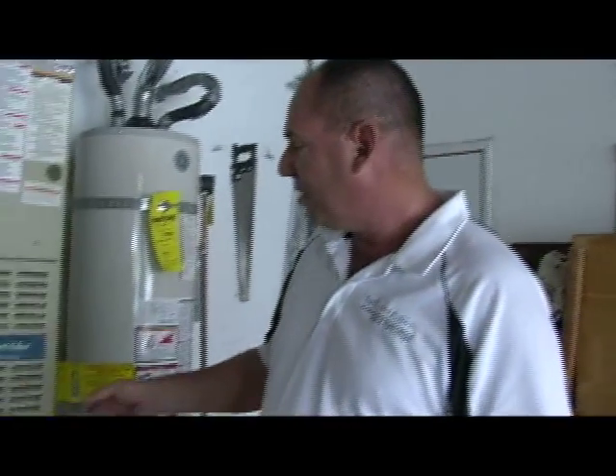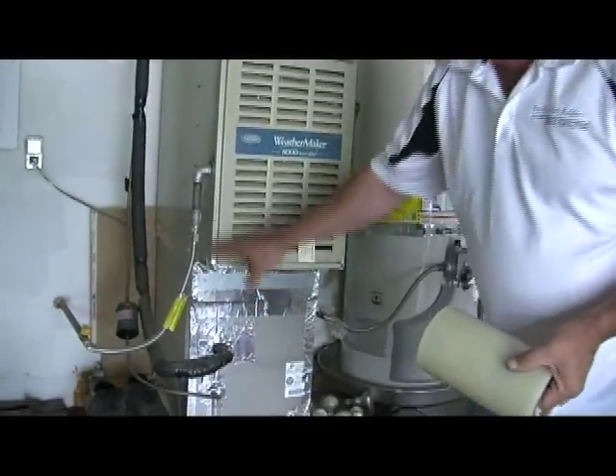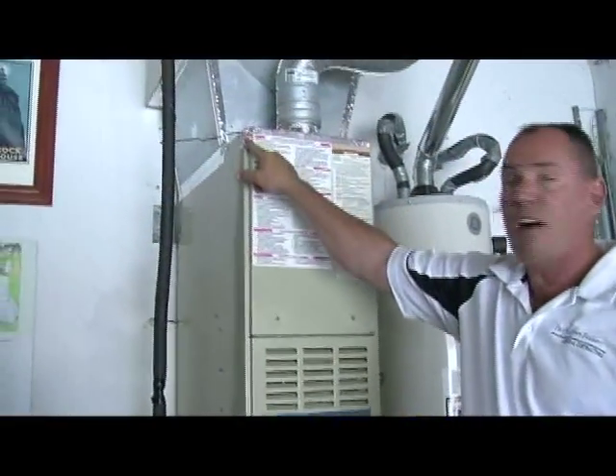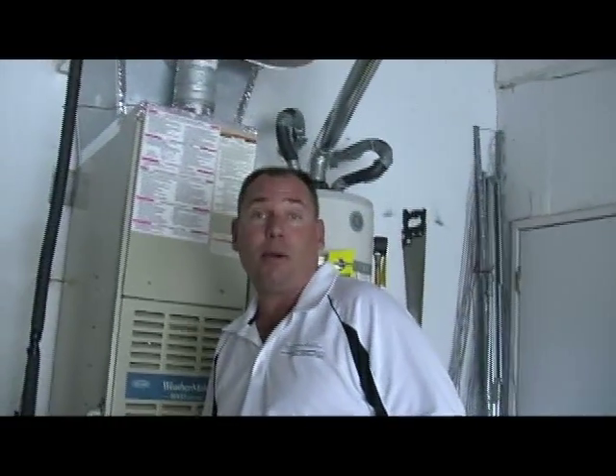There were certain portions of energy savings available to the customer, and one of them, as you can see here, the tape around the unit and in other areas of the house which you're unable to see, is that the system has been totally sealed. We began with what we call a duct test, and the duct test results came out a little over 20%, and with our efforts we have gotten everything down to less than 4% or less than 5. We're hitting 4%, and that's a contribution of the metal tape on the equipment and all the ductwork being sealed and insulated in the best proper form that it possibly can.